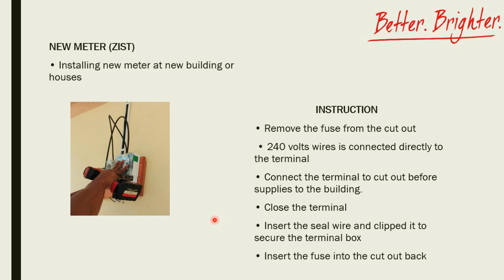First one, we need to remove the fuse from the cutout box. The white box is what we call as cutout box. And then, we need to connect the 240 volt wire directly to the terminal. After that, we connect the terminal to the cutout box before supply to the building. We close the terminals, insert the seal wire and clip it to secure the terminal box, and then we insert the fuse back into the cutout box.